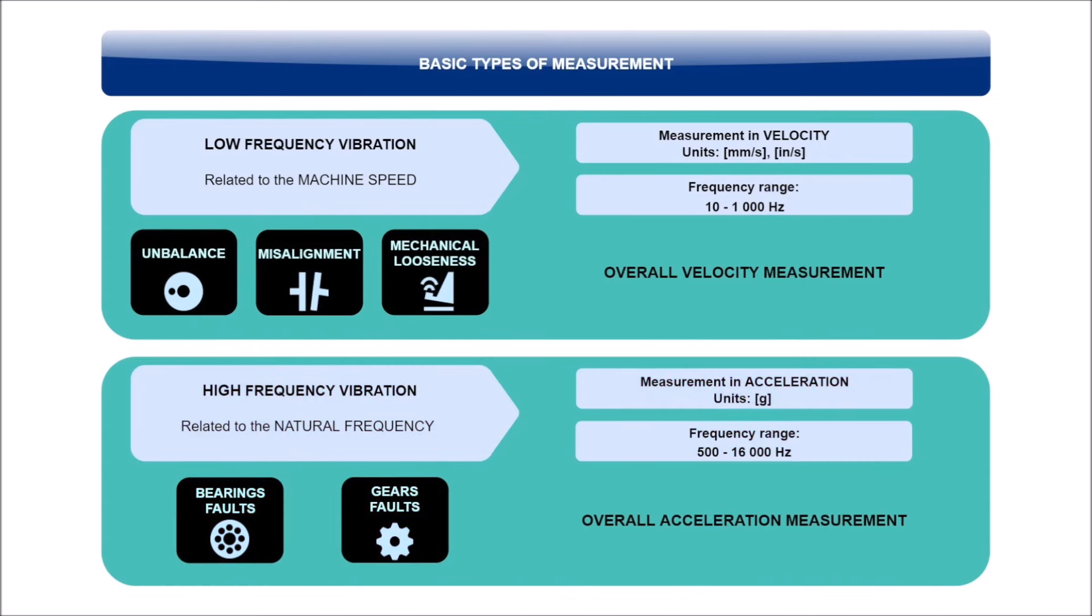Maybe you are asking why we use different units, velocity and acceleration, for those measurements. Put simply, the acceleration is more sensitive to high frequency vibrations, and the velocity is more sensitive to the lower frequency range. So, it has become common to use those two units as they are the most effective for vibration diagnostics.